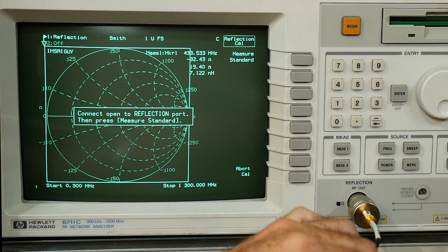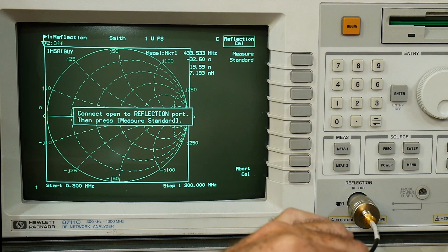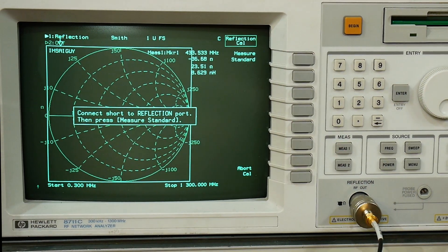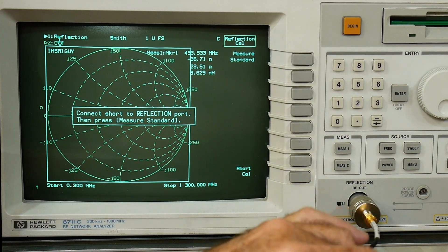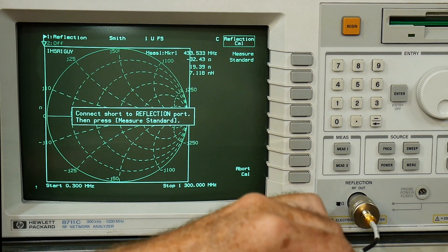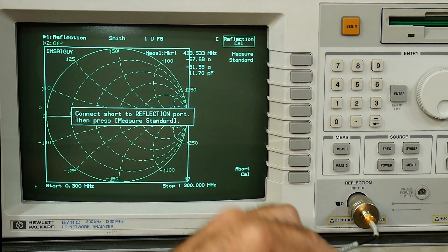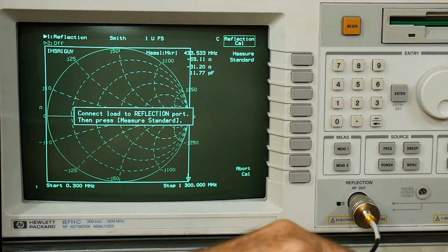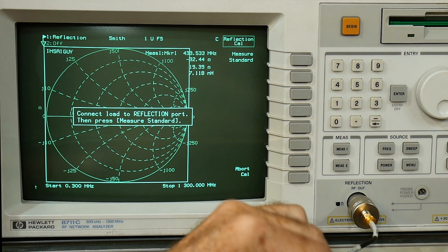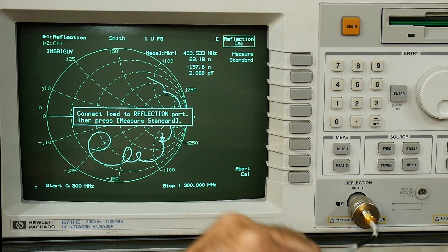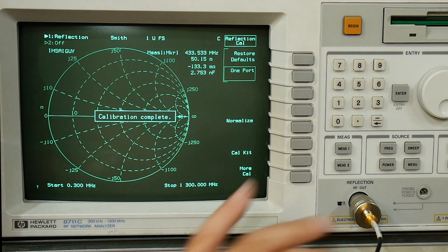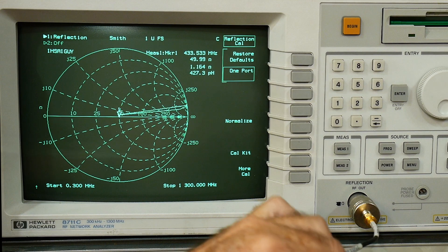Let's calibrate with the short, no open I want to do open first. And then we'll do the short. And then we'll do the load. And now we're calibrated.